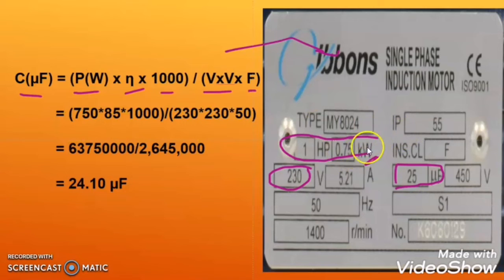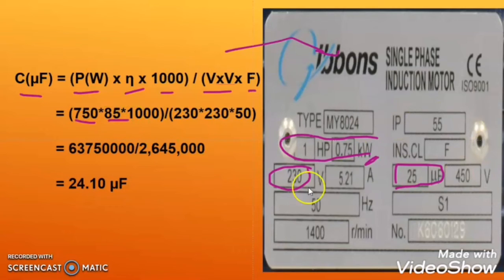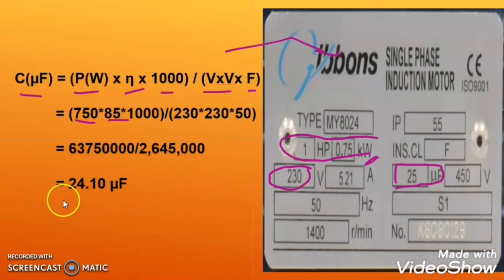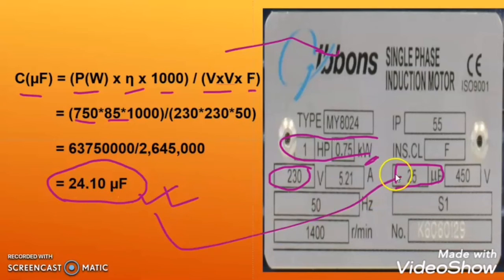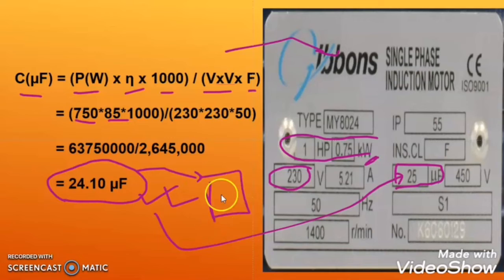The power rating is 0.75 kilowatt, which is 750 watts. Efficiency is not mentioned, so I take 85%. Voltage is 230, and frequency is 50 Hz. When we calculate, we get 24.10 microfarad, which is very close to the nameplate value of 25. So we can use the next standard available size, which is a 25 microfarad capacitor for this induction motor.